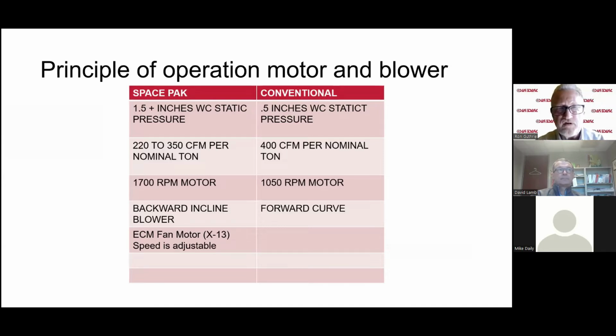These are some differences between SpacePak and a conventional system. We're at about 1.5 inches water column static pressure, maybe just below that. If we get above 1.5, we probably should have more outlets, or shorter outlets. The way we compensate for longer outlets is to put more outlets in, and we'll cover that as well. A conventional system is about 1/2 inch of static pressure. We're at 220 to 350 CFM per nominal ton. I'll tell you right now, because I like to put this number out there, 250 is the sweet spot.